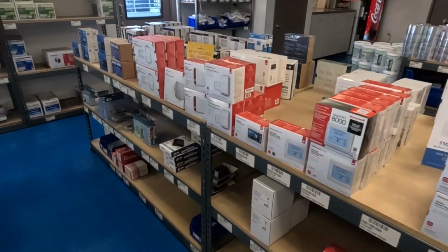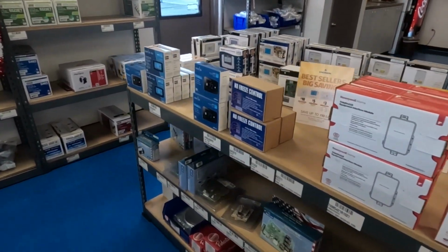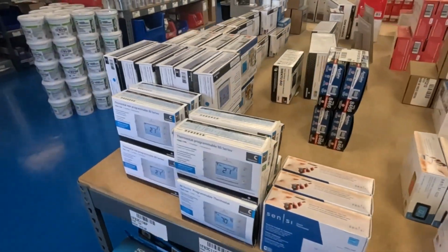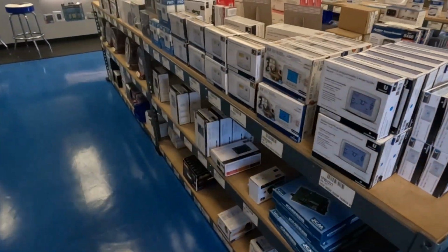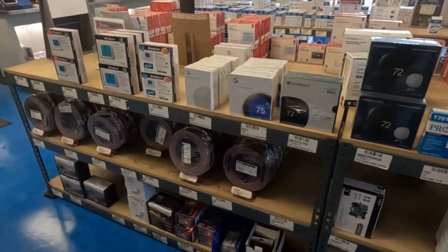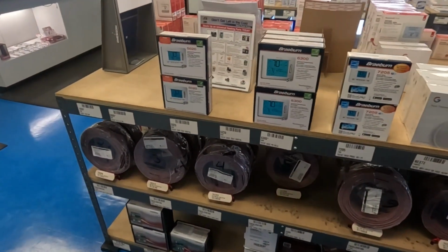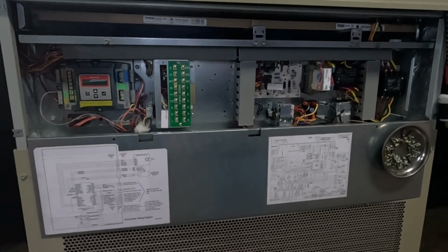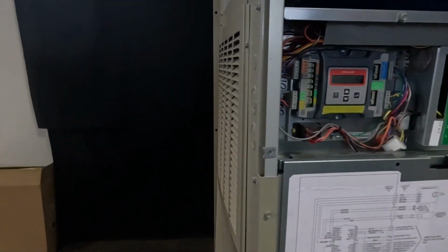You can't be an expert on every thermostat or even to have access to an EMS system. You're simply trying to identify what's not working by a process of elimination: the unit, the stat wire, or the controller. What you may easily eliminate is the HVAC unit. So let's start there. We always strive to isolate the problem by determining what component isn't functioning.